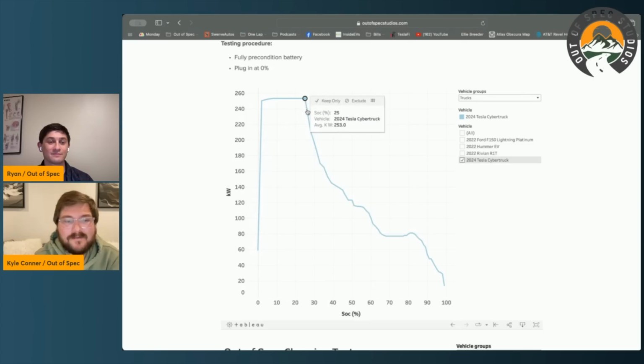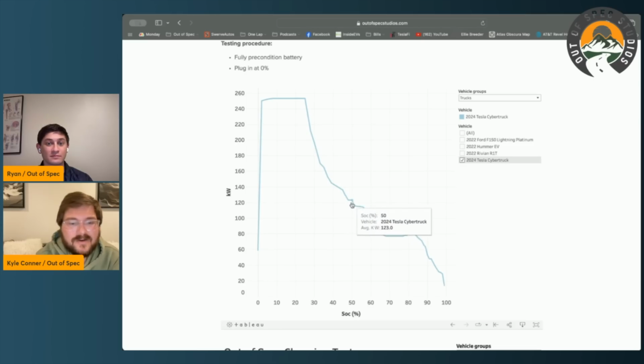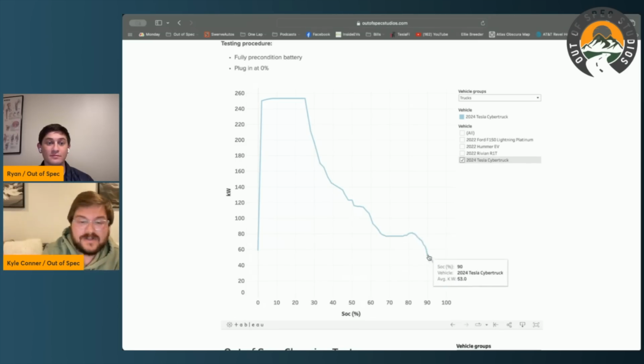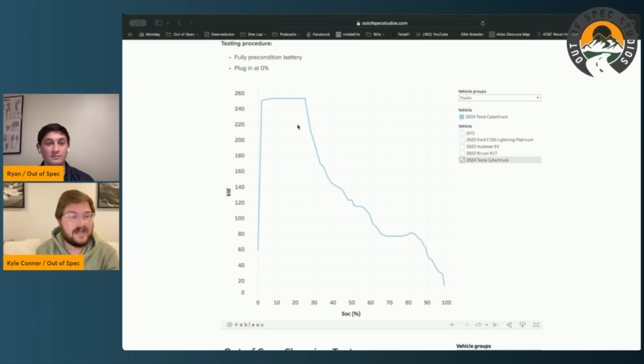After 25%, it just hits a wall. Bam, down. We're talking 165 kilowatts at 35%, 140 kilowatts at 40%. At 50%, it's doing roughly 123 kilowatts, but halfway through 50% there's a ledge every time, and it comes down to about 113 to 116 on average. Then it walks its way down to where at 65% it's really weak. It holds 80 kilowatts all the way to 81%. 80 kilowatts at 80%, that's not bad, I just don't know why there's this ledge. Then it walks its way down to basically a really long top calibration, taking almost 30 minutes to complete charging up top.